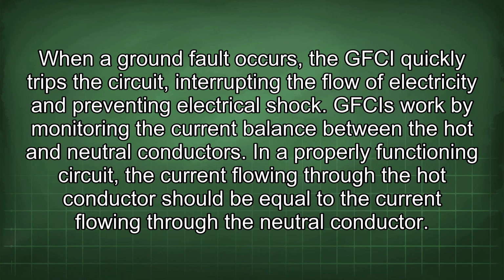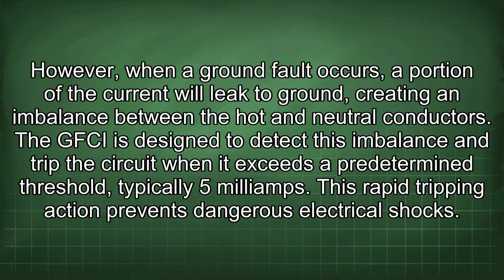GFCIs work by monitoring the current balance between the hot and neutral conductors. In a properly functioning circuit, the current flowing through the hot conductor should be equal to the current flowing through the neutral conductor. However, when a ground fault occurs, a portion of the current will leak to ground, creating an imbalance between the hot and neutral conductors. The GFCI is designed to detect this imbalance and trip the circuit when it exceeds a predetermined threshold, typically 5 mA. This rapid tripping action prevents dangerous electrical shocks.